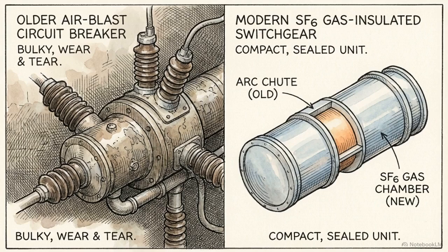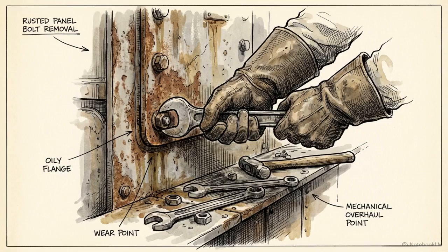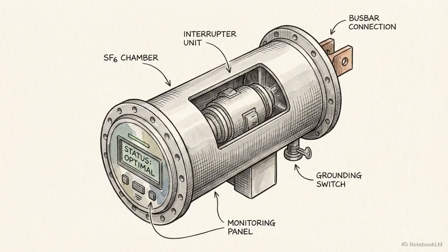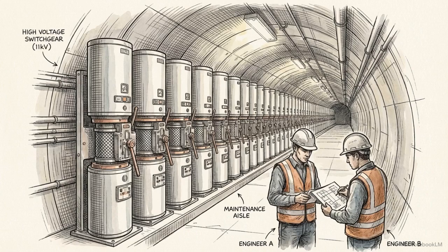First Hydro is currently modernizing this layer of protection, replacing the facility's 1970s-era air blast circuit breakers with state-of-the-art ABB HEC 130 SF6 gas-insulated switchgear. The original air blast technology required a complete mechanical overhaul every 3,000 operations. The new SF6 units are rated for 20,000 operations, extending the maintenance interval to 20 years. Lengthening the life cycle of the switchgear directly minimizes plant downtime. It ensures the station remains fully operational and prepared for the next rapid response grid event.